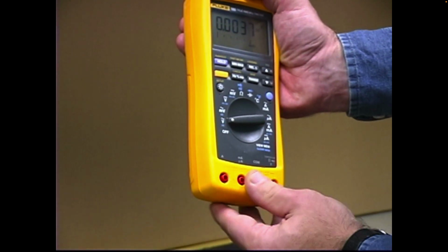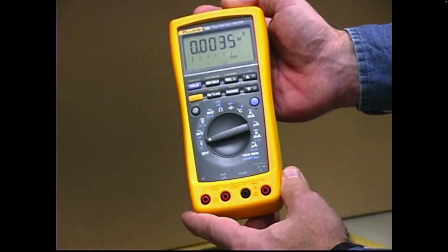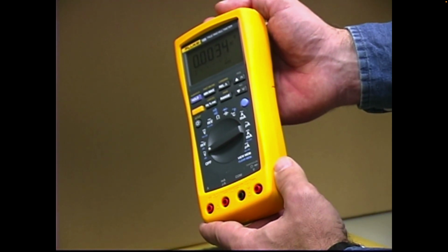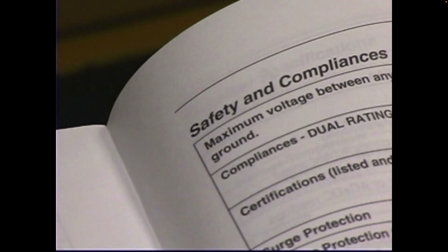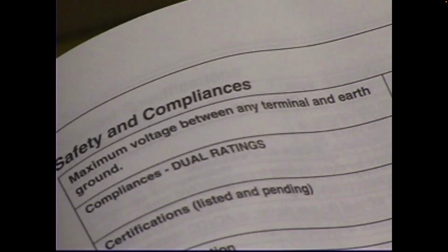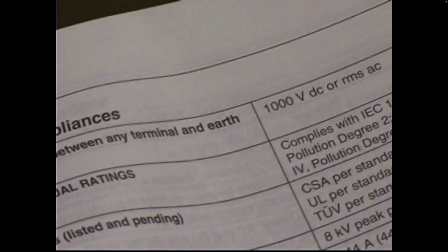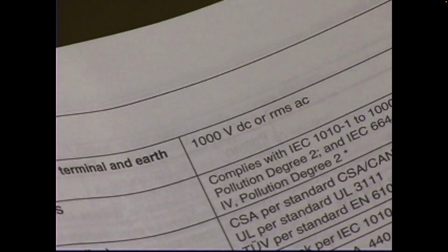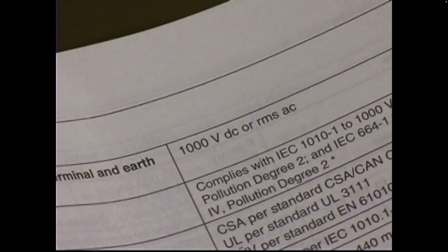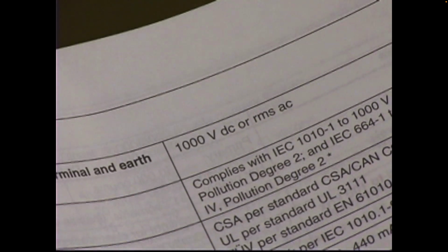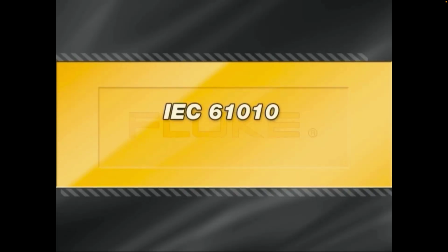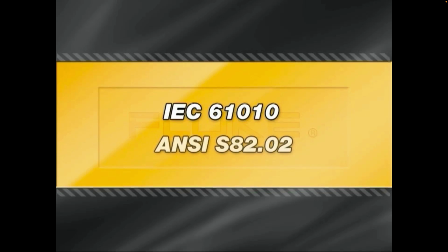Check the condition of your meter or tester. Watch for a broken case, a faded display, or other problems. Check your manual to see if the ohms and continuity circuit is protected to the same level as volts. If the protection level is not listed, ask for written confirmation from the manufacturer. The relevant standards are covered in IEC 61010 or ANSI S82.02.